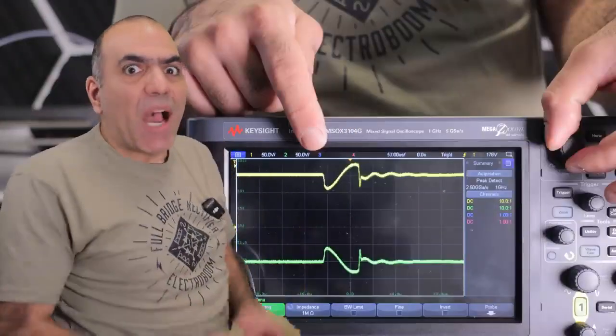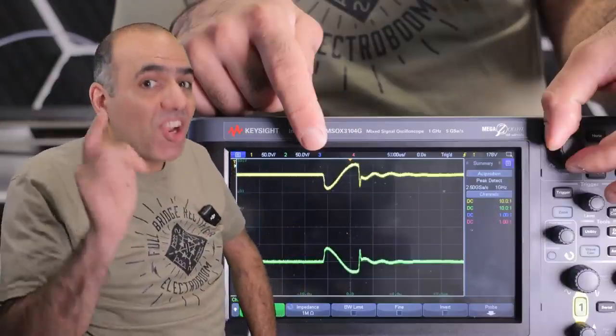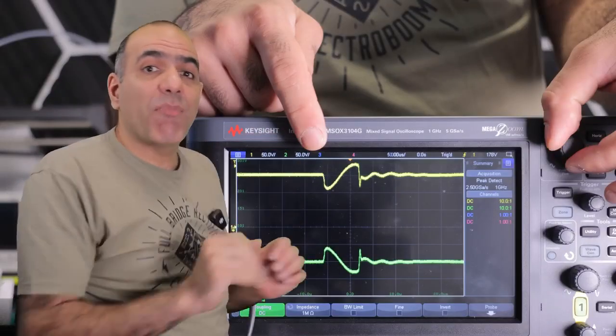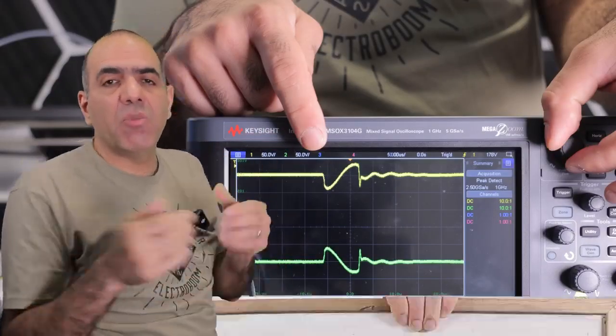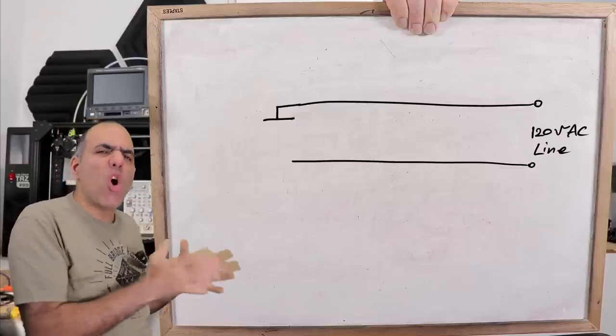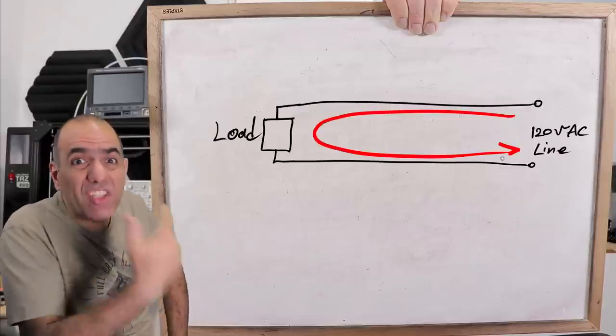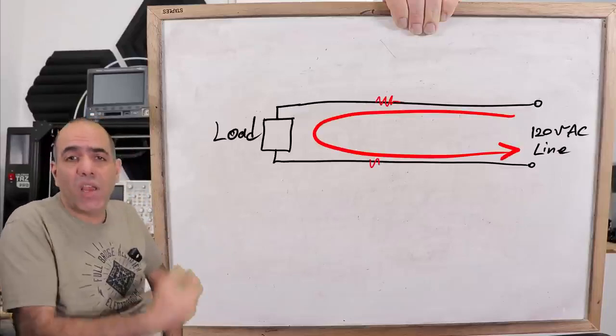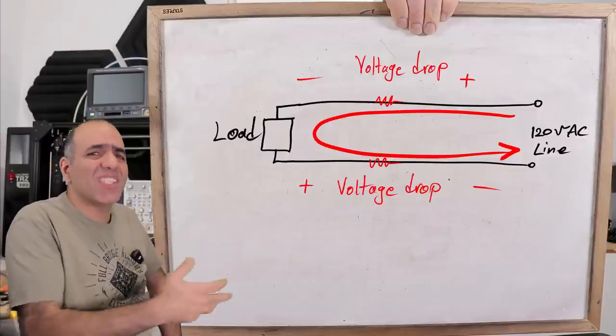It's guessing time: how did they make this happen? Because we see a drop on positive power and a rise in negative, it means they're connecting a large load, drawing a ton of momentary current between the lines, and the line voltage drops over wire resistance and inductance.